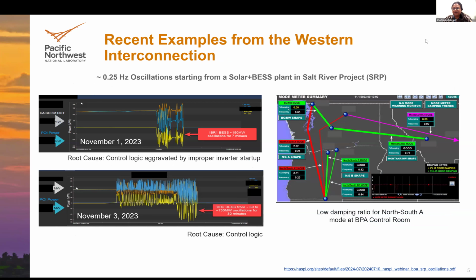Due to erroneous reference points being fed by the plant controller, the units within the plant injected oscillations at around 100 megawatts and 0.25 hertz into the system. And because 0.25 hertz is close to an inter-area mode in the Western Interconnection, the North-South A mode, there was an interaction. Because this oscillation was at a low frequency, this oscillation, which was injected by one plant in Arizona, was observed throughout the Western Interconnection. The figures to the left are what SRP saw. And the figure to the right shows what was seen in the control room of BPA, or Bonneville Power Administration. They are a transmission utility in the Northwestern region.